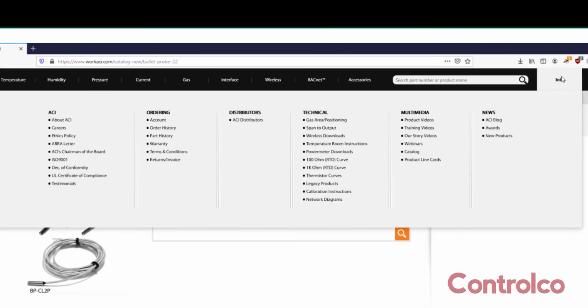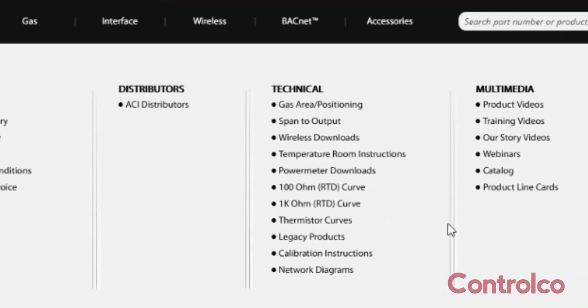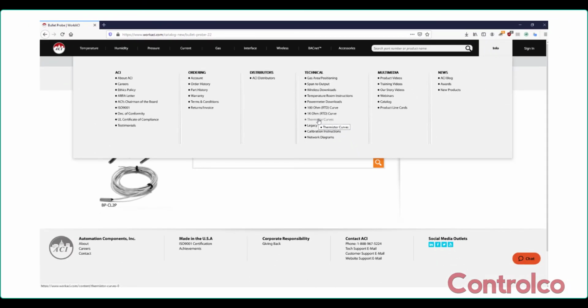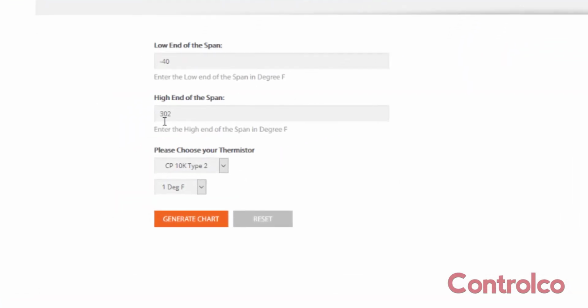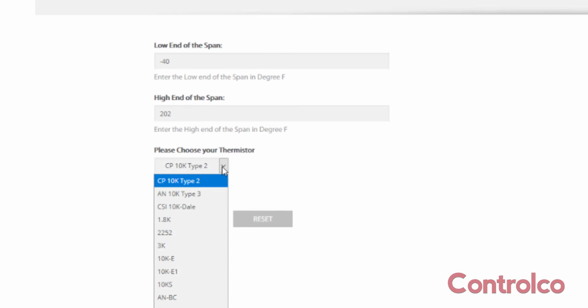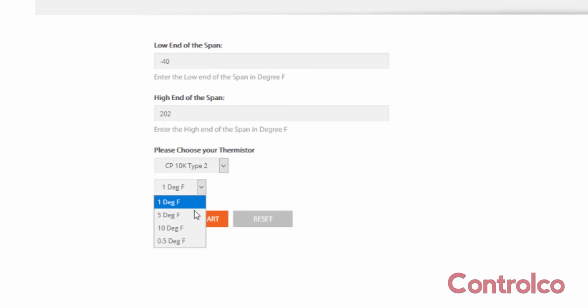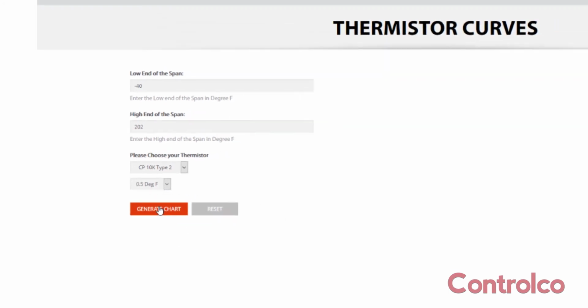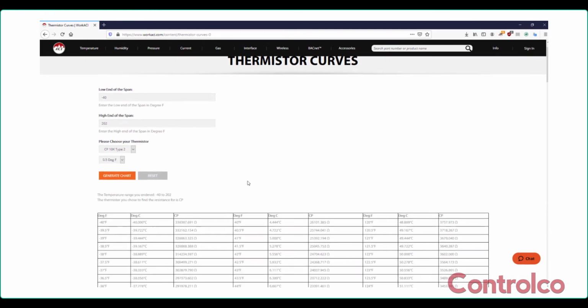But that chart doesn't really have it either. So this is the cool part. They have a thermistor curve, and it allows you to input some values. So I'll just put minus 40 to 200 and something. And then I can go down and choose the thermistor that I'm working with, the type. So this is a type 2. My Johnson Controls is a type 2. You can see there's some other options in the list. And then I want to generate a chart in half-degree increments. So I'll generate that chart, and I'll go down the list until I find something close to what I had.